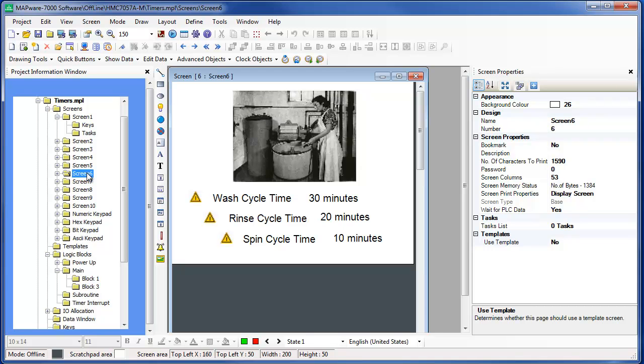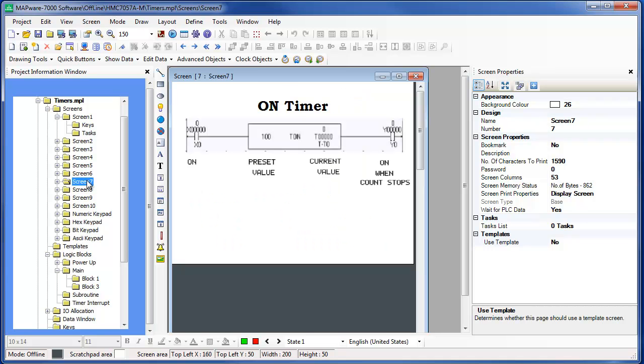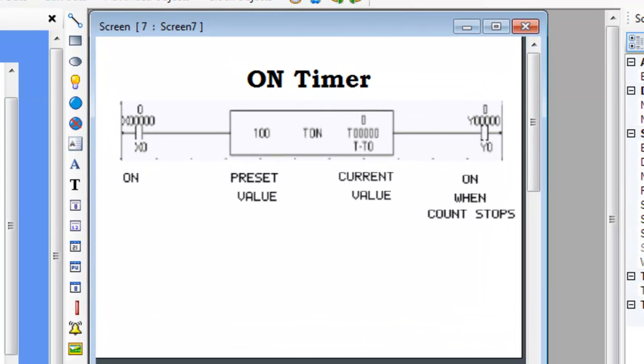The Mapware 7000 software supports three timer functions that can be used in ladder logic. The on timer counts while the input is on. When the preset time value is reached, the timer stops counting and the output turns on. Setting the input off resets the timer to zero and also turns the output off.